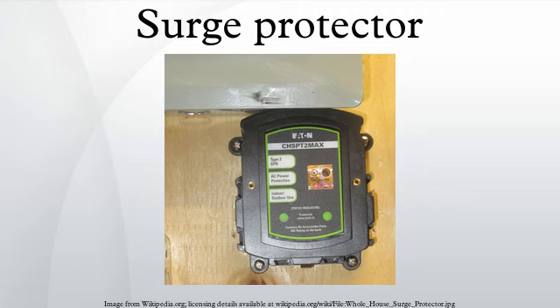Important specifications. These are some of the most prominently featured specifications which define a surge protector for AC mains, as well as for some data communications protection applications. Clamping voltage, also known as the let-through voltage. This specifies what spike voltage will cause the protective components inside a surge protector to divert unwanted energy from the protected line. A lower clamping voltage indicates better protection, but can sometimes result in a shorter life expectancy for the overall protective system. The lowest three levels of protection defined in the UL rating are 330V, 400V and 500V. The standard let-through voltage for 120 VAC devices is 330 volts.